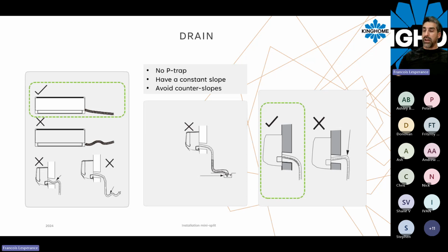When it comes to the indoor portion, well, now we're talking about the drain. The drain is really important to get right the first time. Even when you do some maintenance on the unit, make sure you test the drain properly. You have no P-traps, you have a constant slope, and you avoid counter slope.